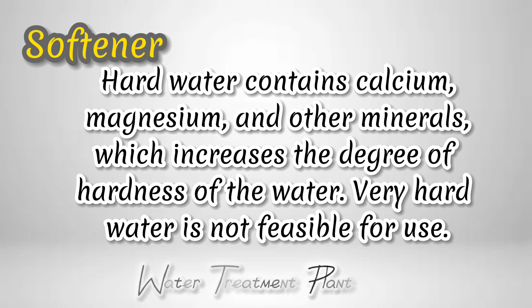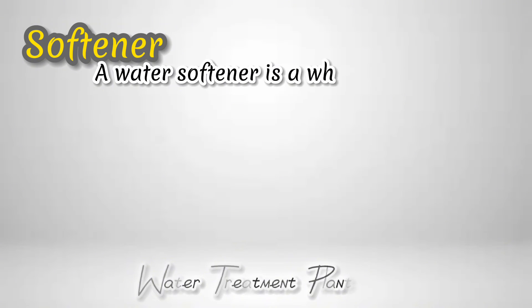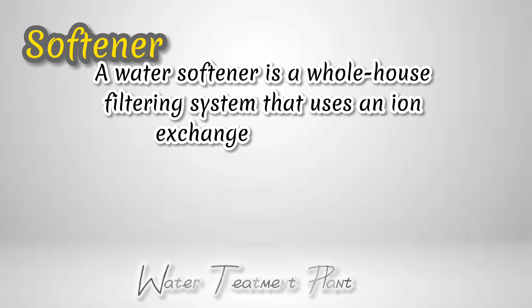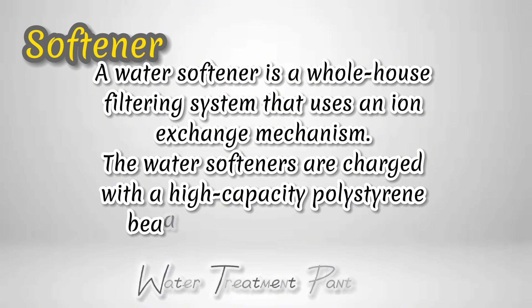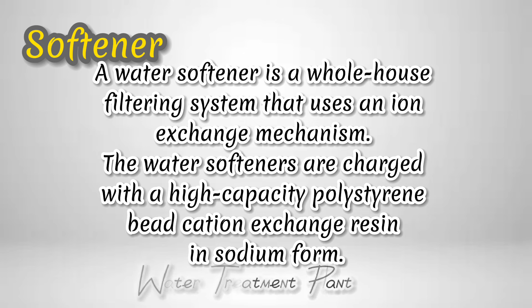Very hard water is not feasible for use. A water softener is a whole-house filtering system that uses an ion exchange mechanism. The water softeners are charged with a high-capacity polystyrene bead cation exchange resin in sodium form.